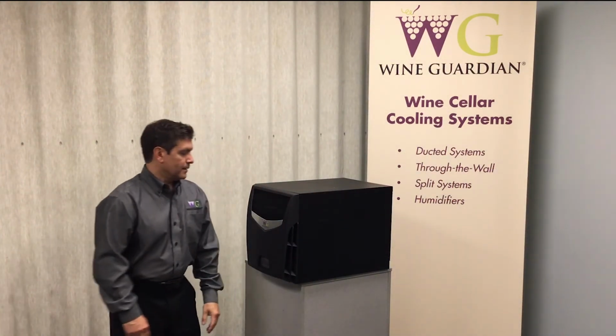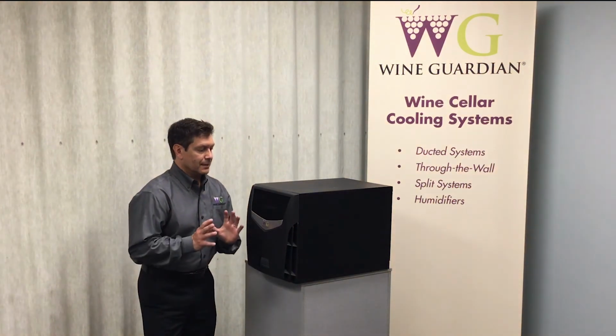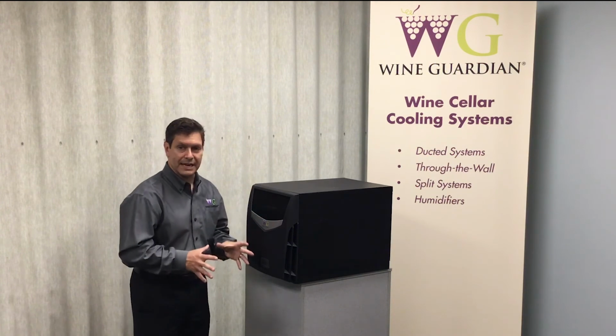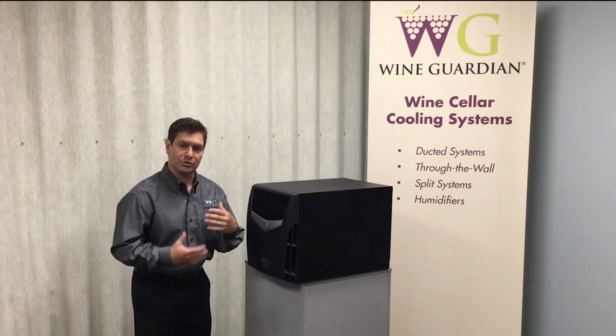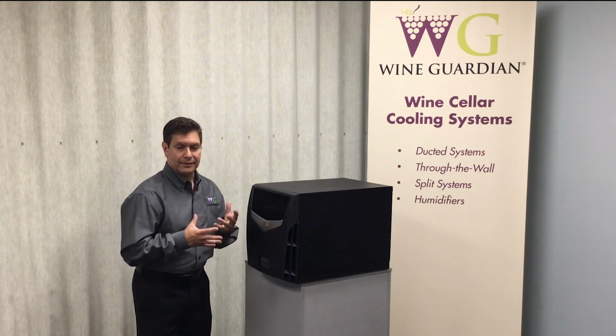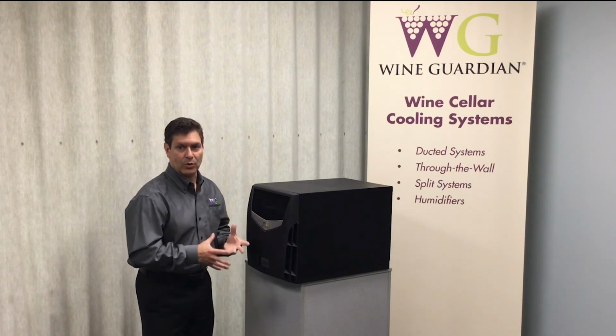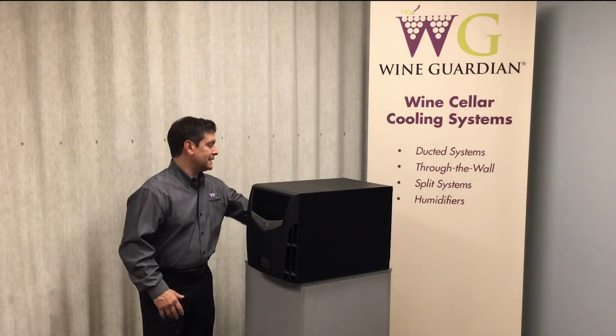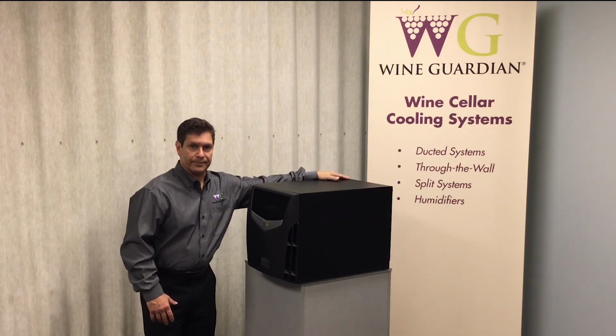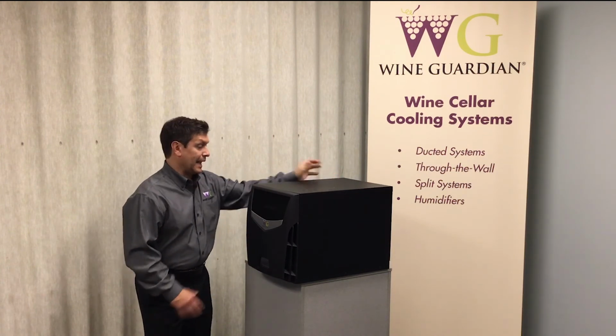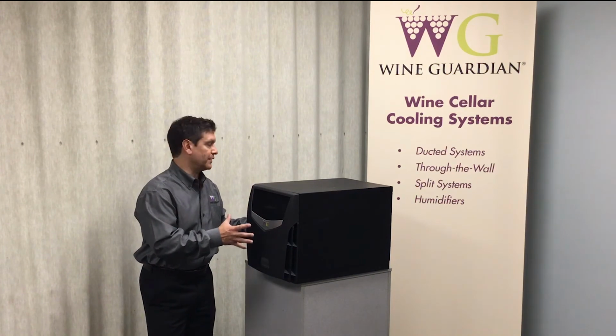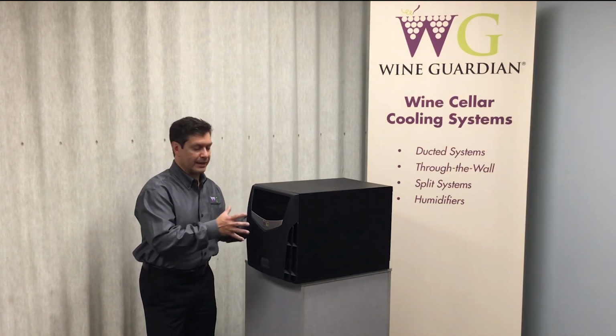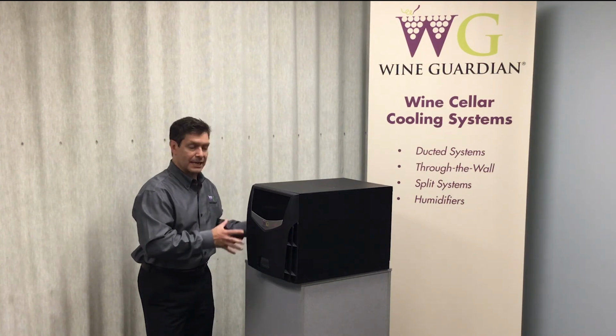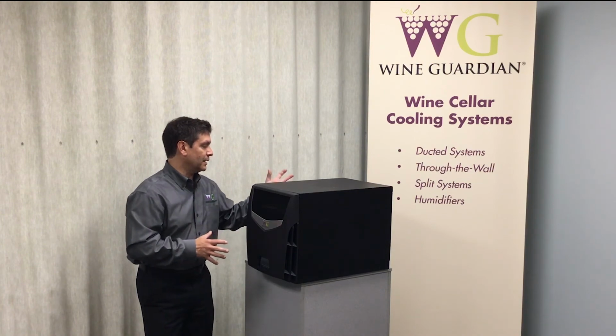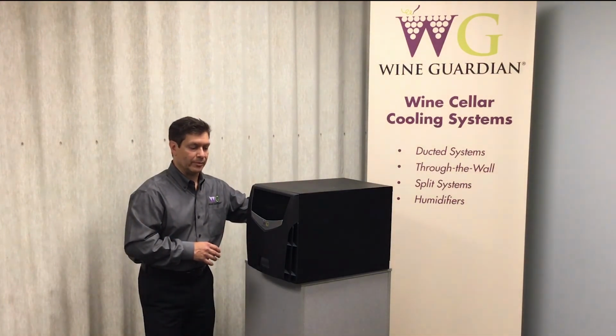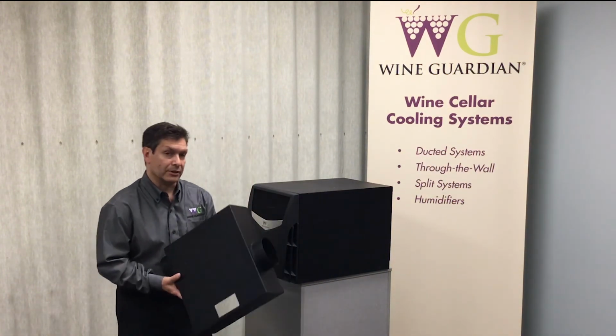Can the whole unit sit inside the room? Generally, most of the time, the wine cellar cooling unit, because it's a through the wall, goes through the wall of the wine cellar. You can mount the whole device inside the wine room, but you have to have an intake and exhaust on the condenser side of the unit. That's the only way that the system will work. And you also have to accommodate for the size of the unit. So you have to have enough space to accommodate the roughly 25 by 16 and a half inch size of the unit. So as long as you can accommodate that and you can bring in air and exhaust air out of the wine room using one of our duct collar connections, you can do that.